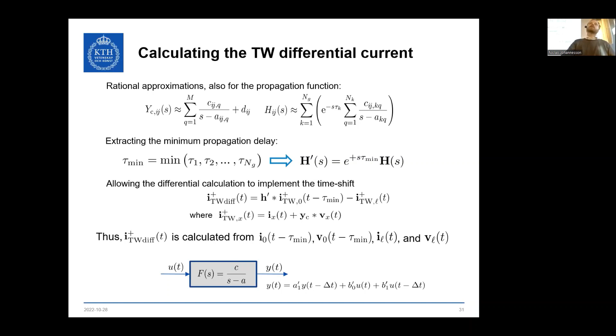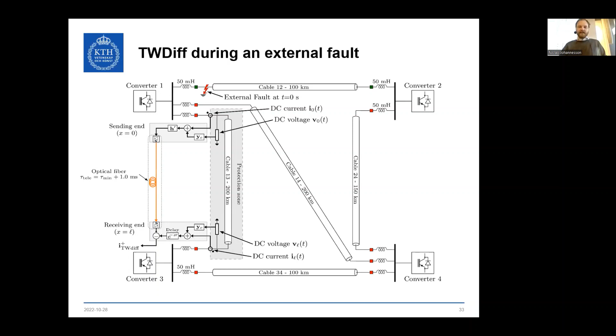So again, this very nice 4-terminal circuit, courtesy of Leuven, I guess. So here I simulated an external fault. I guess voltage and current are not that interesting, but to the bottom right here, the blue one is the wave on the sending end. So this is the wave that, immediately when the fault happens, you can see it's entering the line. The red one is obtained by applying the distortion to the wave that you calculated. And the green one is the wave that you measure on the receiving end. As you can see, the red and green one are more or less identical, except for this time shift. And then calculating the difference between them, you can see it's strictly 0.